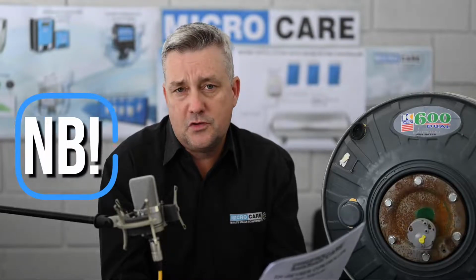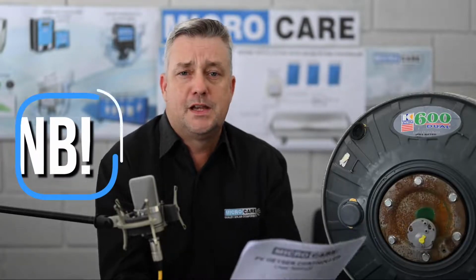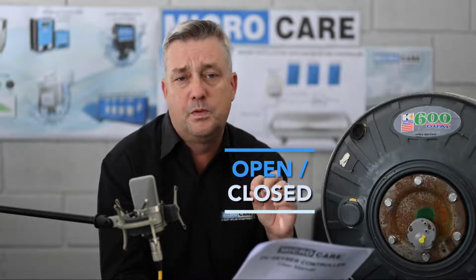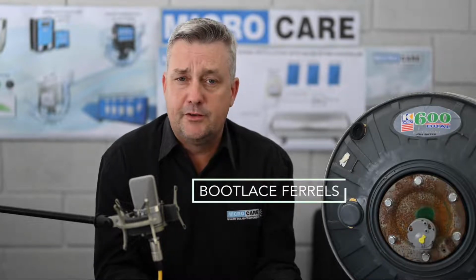It's very important, if you've not worked with a connector block before, that you make sure that it is open or closed before you start inserting a cable. The correct thing is to open it completely if it's not already open, and then close the clasp over the connection. We will talk a little bit about bootlace ferrules, making sure you've got a clean connection there within the Geyser Controller. I'll move over to page 4.